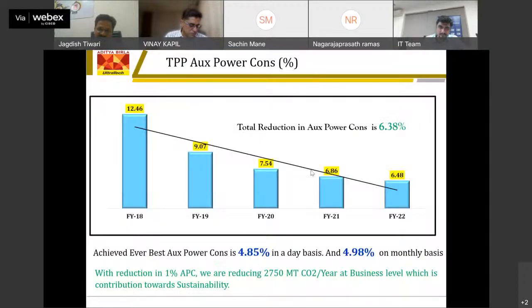Coming to the performance, sir, this Dala unit we took over from Jaypee Associates Limited in June 2017. At that time, auxiliary power of this unit was 12.46% in FY18. Then we made a lot of improvements and reduced the auxiliary power in FY22 to 6.48%. That is a reduction of near about 6.38% in the last 4 or 5 years. And monthly we have achieved less than 5%, which is the benchmark in our group units, in UltraTech units.